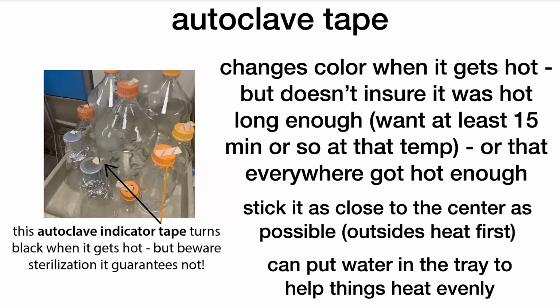You also want to stick the autoclave tape as close to the center of something as possible. It's kind of like a microwave, where the outside gets hotter first. So if you stick the tape just on the far outside of something, that's going to get hot and the autoclave tape is going to change color, but the insides of things won't get hot enough to actually sterilize them.